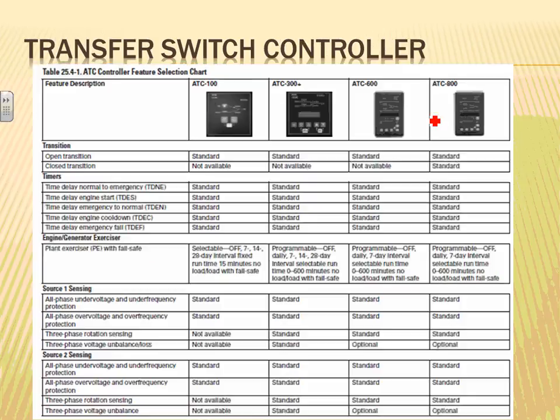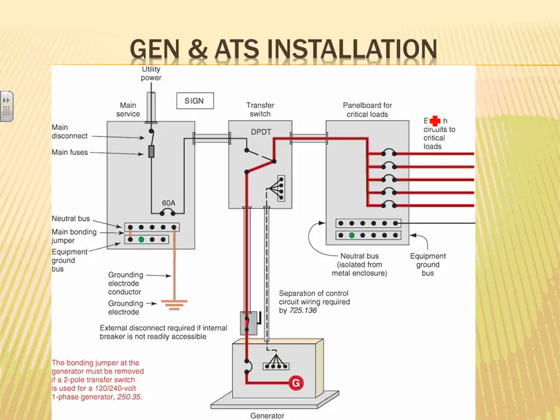And they size them in different enclosures. They're smart auto transfer switches, guys, very smart equipment. This is the switch controller that comes with them. They can sense open transition, closed transition. You can see each one of these controls can decide whether you're going to go open or closed. They can sense voltage and frequency. You can pick a lot of information out of the controllers. Any comments, guys, any questions? I leave the details to the manufacturers of the switchgear.